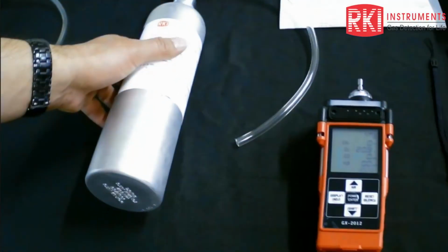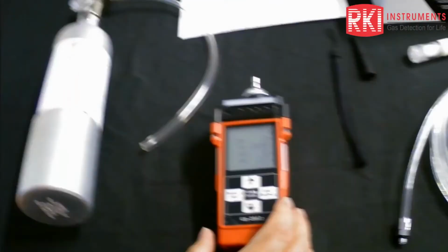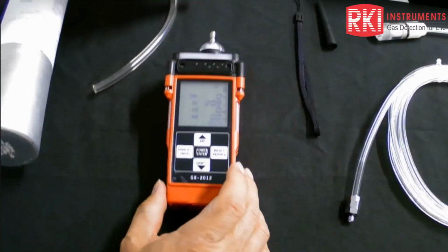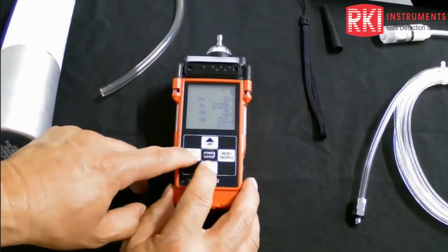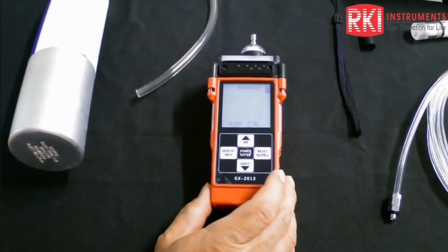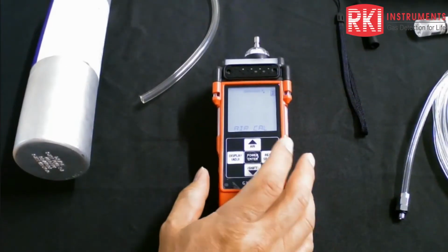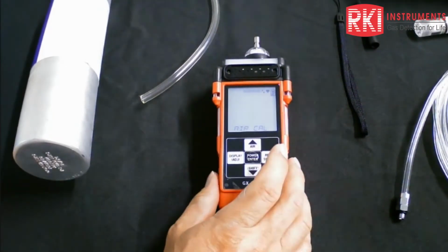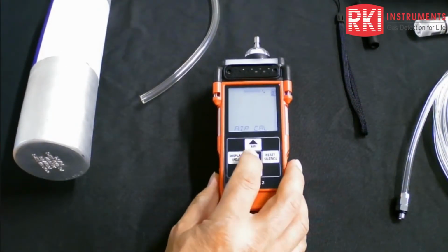Okay, so what I'm going to do next is get into the Cal mode, which is going to be press this shift down button and the display. Okay, the first thing that comes up is air cal. So I'm going to do an air cal to show you that function. Okay, so I'm going to press the enter button to select that.